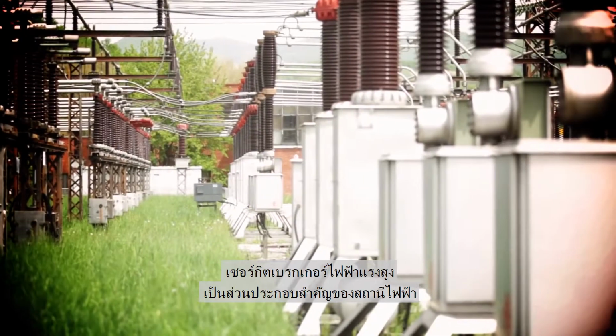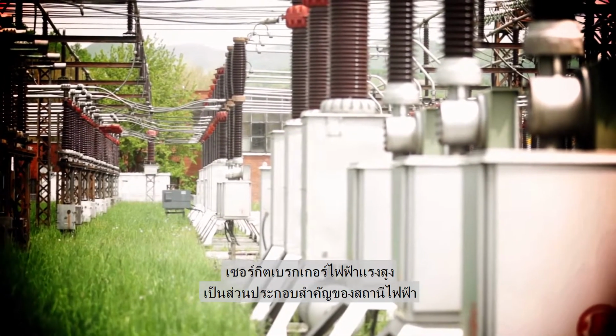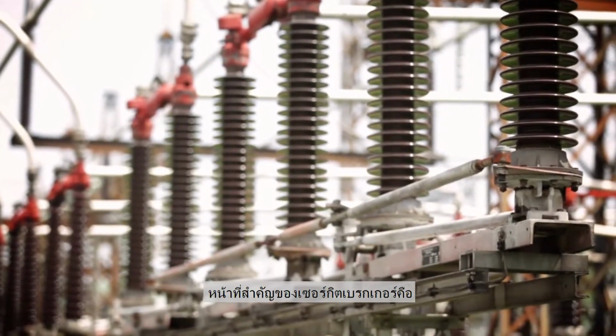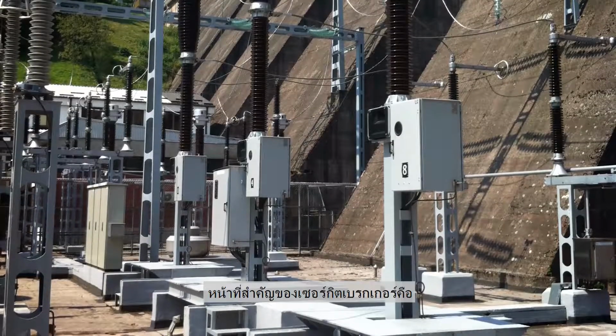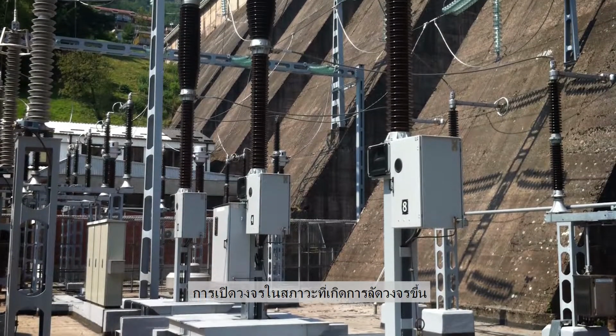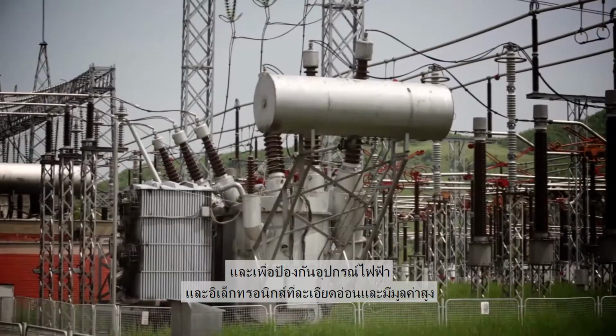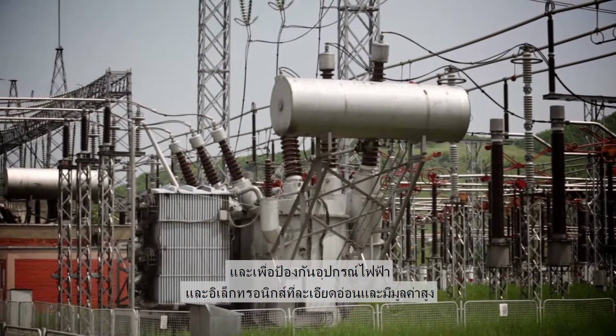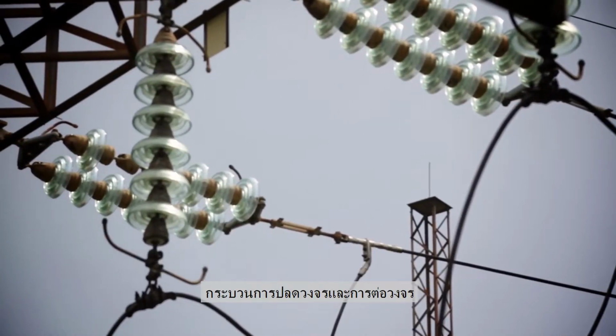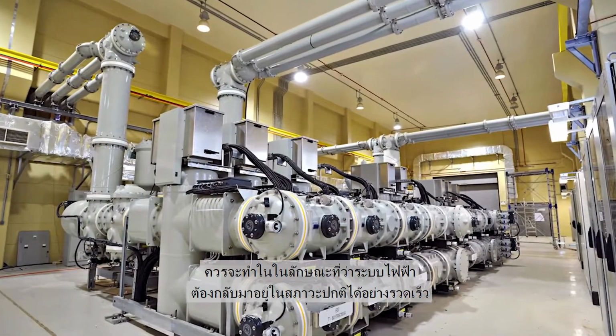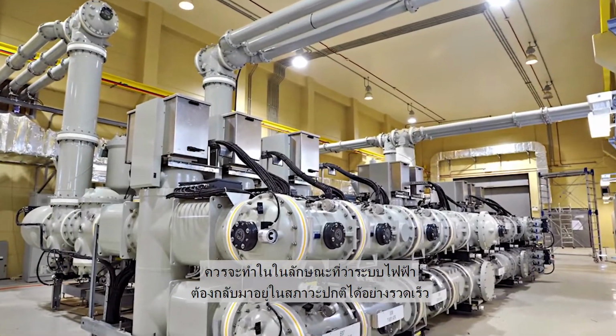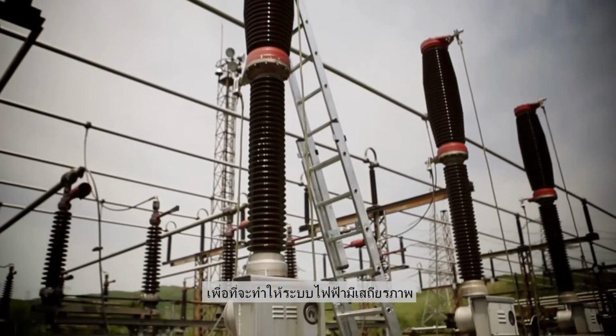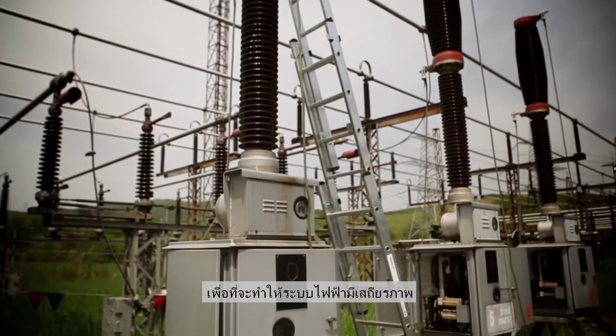High voltage circuit breakers are some of the most important components in the substation. The most important task of a circuit breaker is to open circuits under short circuit conditions and thus protect sensitive and expensive electric and electronic equipment. The interruption and the subsequent reconnection should be carried out in such a way that normal operation of the network is quickly restored in order to maintain system stability.